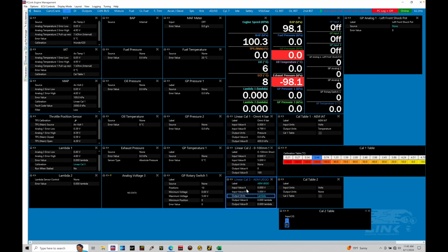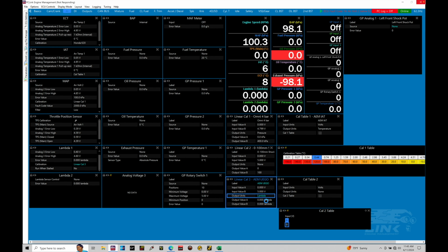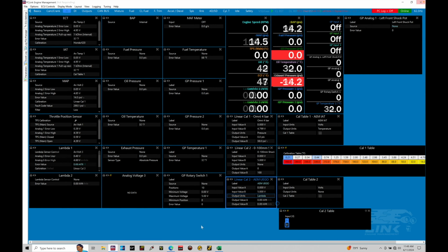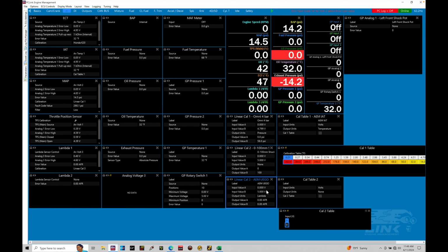And we should find, when we go ahead and select that, that the units here should correlate to air fuel. It looks like it's taking a second for that to take. We'll just be patient until it converts. So we can see here now that the units have been updated to units of petrol air fuel, which allows us to go in and set up our A and B outputs. So it's going to match the scale here, the min and max voltage. Going back to our data sheet real quick, we're going to find 0 volt is 10 to 1 air fuel. So we're going to populate that right here.